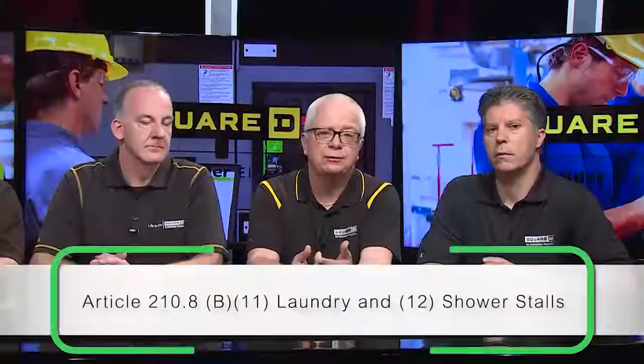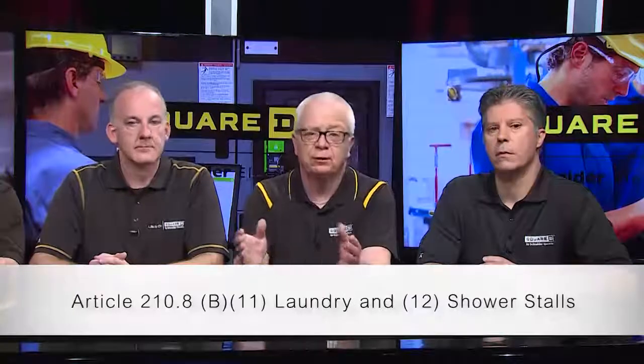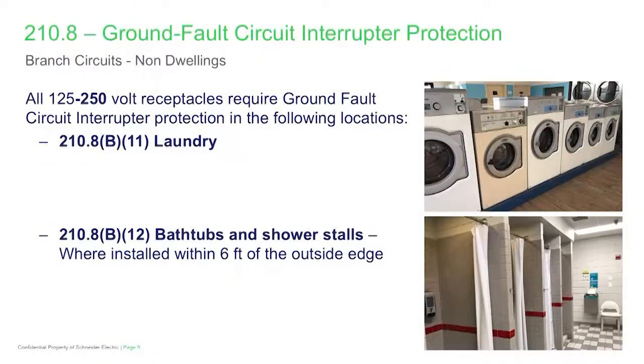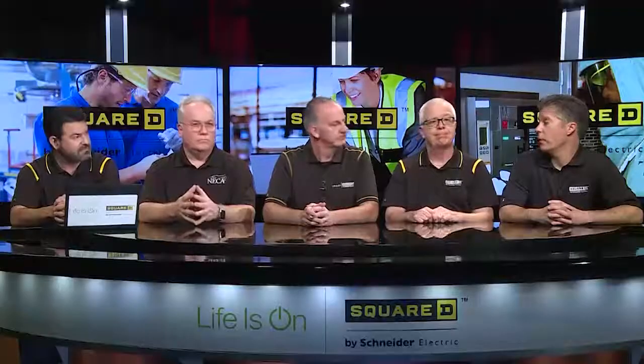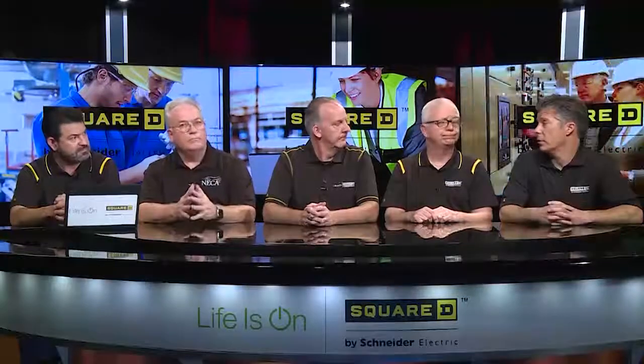The next piece is in 210.8(B)(11) — there's a new list item there. Other than dwelling units would be laundries. So if you've got a laundromat and you've got receptacles, everything needs to be GFCI protected. We also address in 210.8(B)(12) bathtubs and shower stalls — that's going to be within six feet of the outside edge of a bathtub or a shower stall. We're recognizing the hazards are the same — let's protect people with GFCI protection.